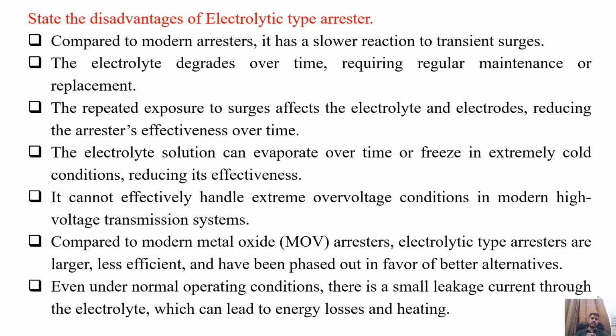It cannot effectively handle extreme overvoltage conditions in modern high voltage transmission systems, and because of this they are replaced. Compared to modern metal oxide arrestors or MOVs, electrolytic type arrestors are larger, less efficient, and have been phased out in favor of better alternatives. Even under normal operating conditions, there is a small leakage current through the electrolyte, which can lead to energy losses and heating during operation. So these are several disadvantages of the electrolytic type arrestor.